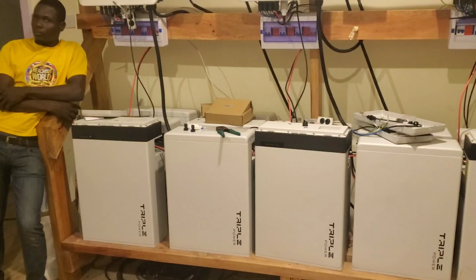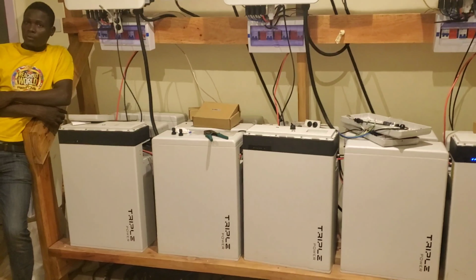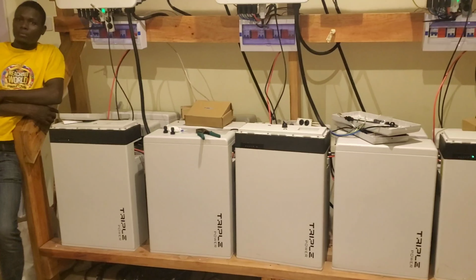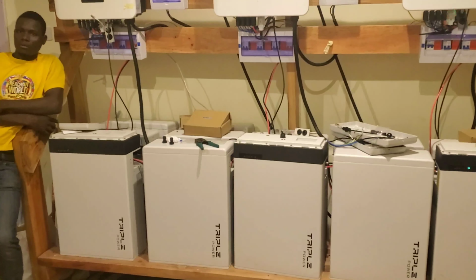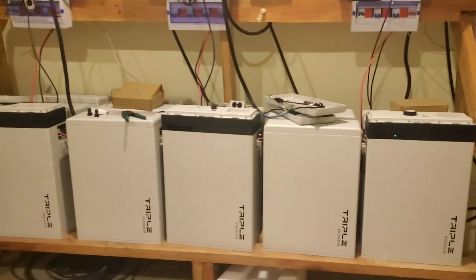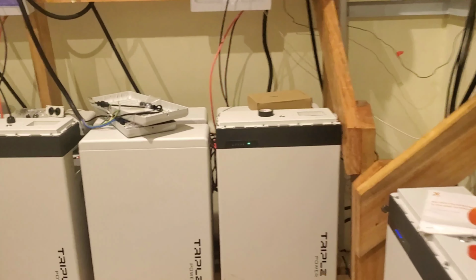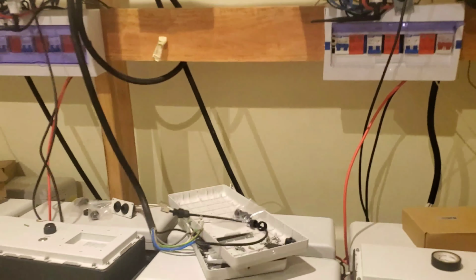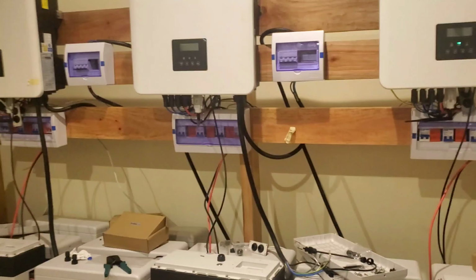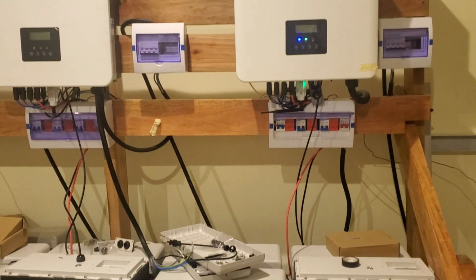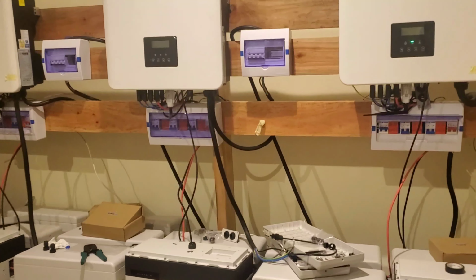Right now, with minus 1 inverter, we would have had 44. But now it's 2 inverters, it would have been 40, because 2 inverters are offline. So it's the same thing. What else? I have no clue what to say. It's just driving us nuts. The manufacturer is a little slow to respond because they don't have experienced people. The people that sold us this inverter in South Africa made some errors. They didn't do their calculations properly, and they gave us an inverter which doesn't work. If they had tested, they would have found the issue, but we'll forgive them.